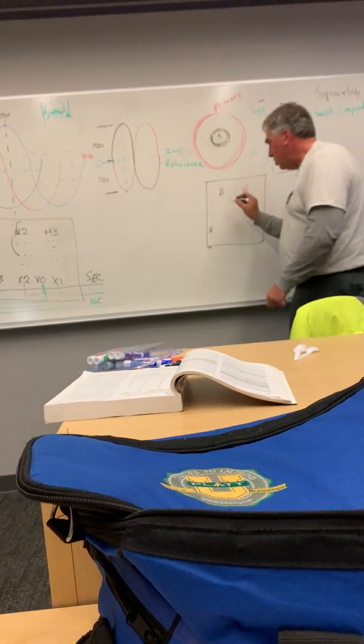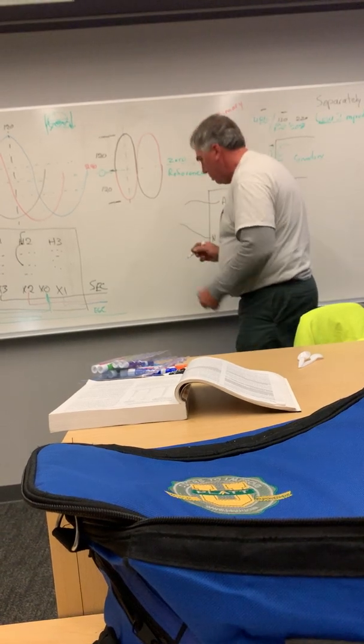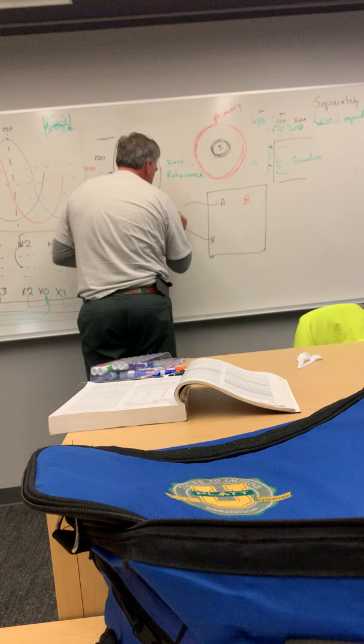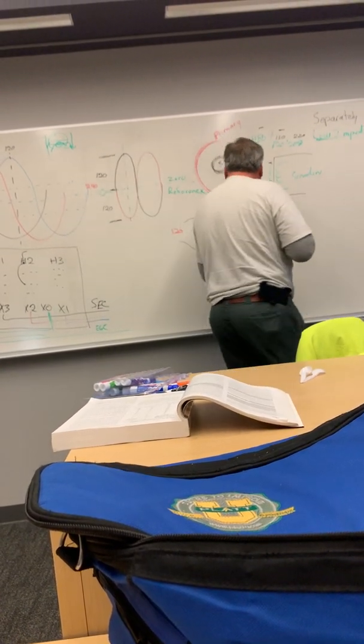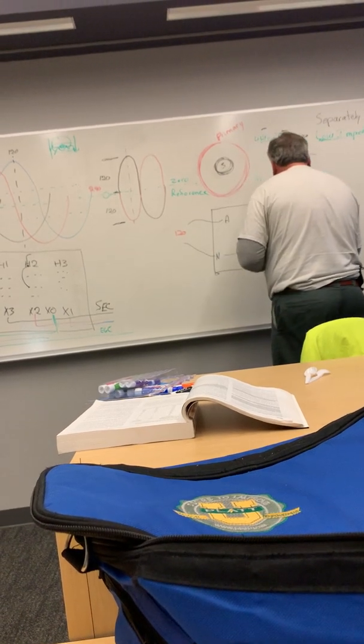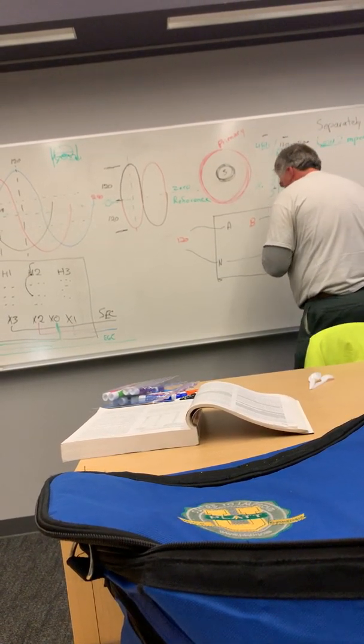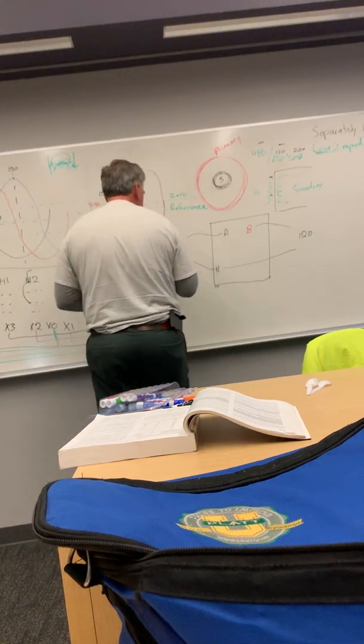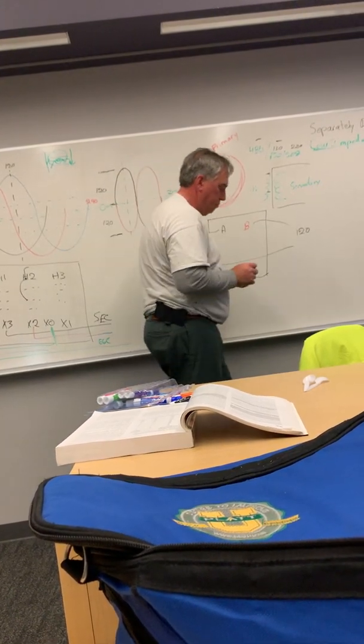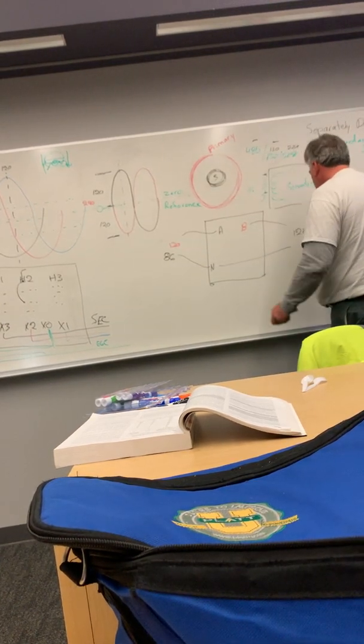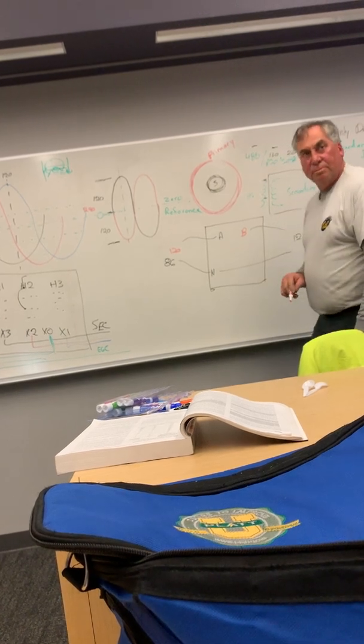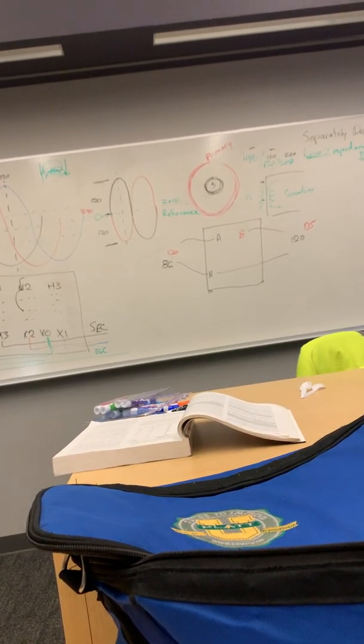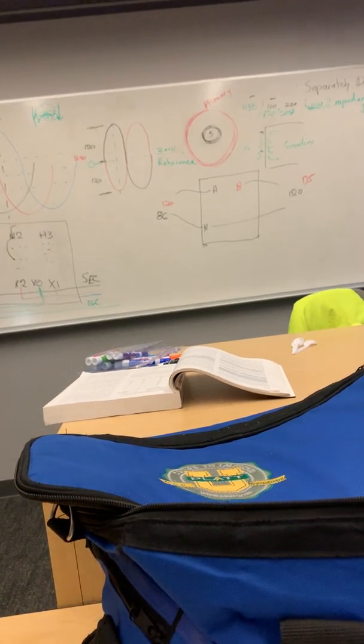So then I took two meters. I took one meter over here, and it says 120 volts. I take this meter over here to neutral, and it says 120 volts. I said, okay, go ahead and do what it was doing before. All of a sudden, this one is 86 volts, this one is 135 volts, and it's jumping all over the map. That's because the demands on the system are creating its own neutral now. It's doing whatever it wants because there's no zero reference.